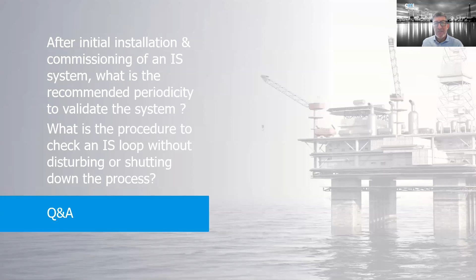There are some boxes out there, Bob, that I've seen. There are stainless steel EXD boxes, no? Yeah, there is. They're cast. They're usually welded type stainless steel, big thick walls. And so you cannot put a gland plate on those. No, no, they still have to be drilled and tapped like a sand cast aluminum type.